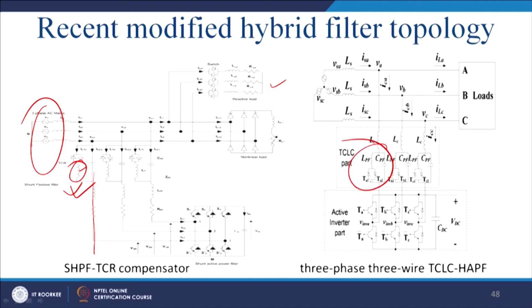and ultimately the harmonic part will be fed to this L and C. This will be tuned to the particular dominating harmonic, and thus you can get rid of it. Essentially, if you see LC and CPF, this is nothing but the same topology. Within that you have a controlled inductor through switching, and thus you essentially have a 3 phase 3 wire TCLC hybrid active power filter.